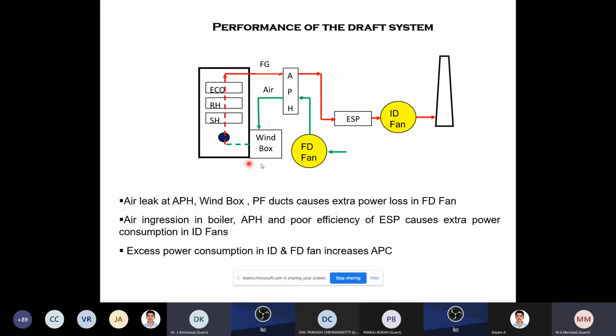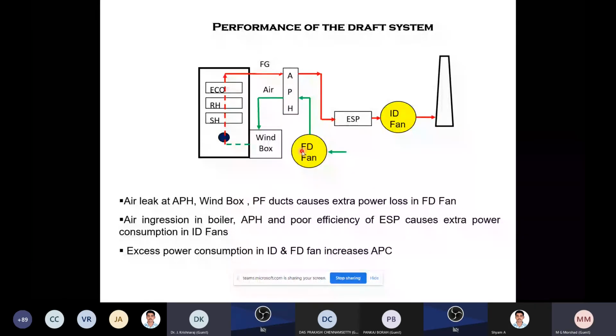In this air circuit, on this side the FD fan is loaded. If there is a leak, air will come out. If there is a leak in the wind box, in the PF duct, or in the air heater, what will happen? Unnecessary air has to be sucked by the FD fan. Only part of it, about 70%, will be useful and 30% will be waste. In such cases the FD fan will consume more power.